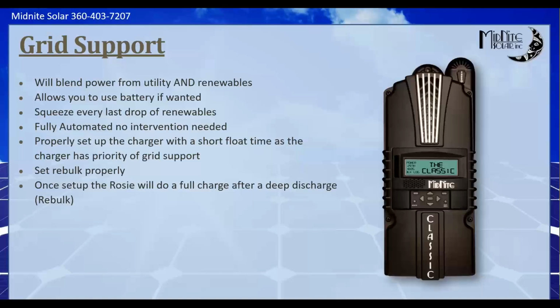Some of the things that we're going to need to do is to properly set up the charger with a short float time. This is one that I get a lot. The Rosie, by default, has a 24-hour float timer in it. So what that means is that if a Rosie connects to the grid, it will do its bulk charge. Then it will do its absorb charge for the absorb time you have programmed. Then it'll drop into float, and it will stay there for the remaining of the 24 hours until a new absorb cycle is triggered at midnight.